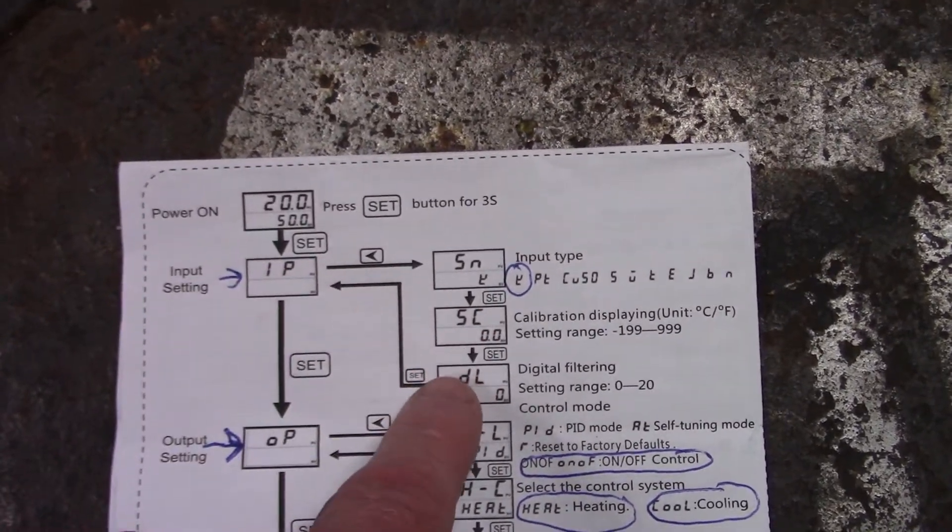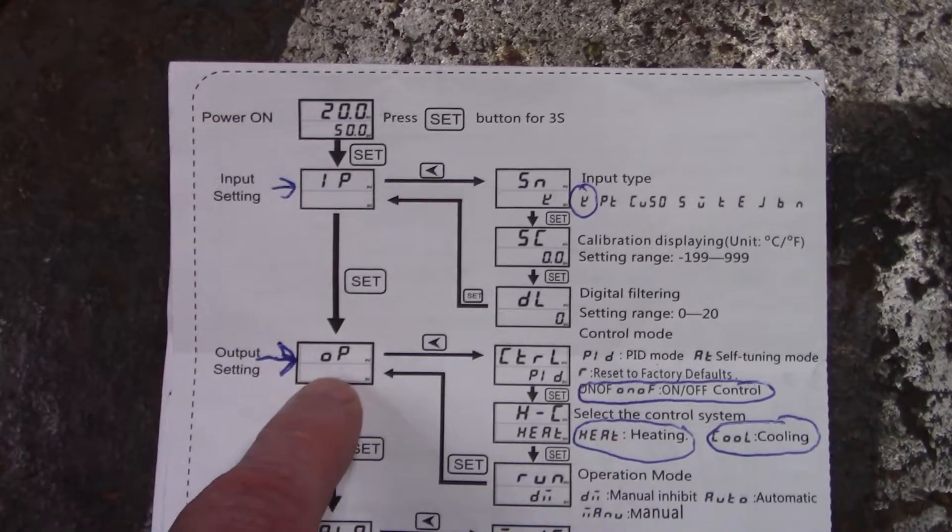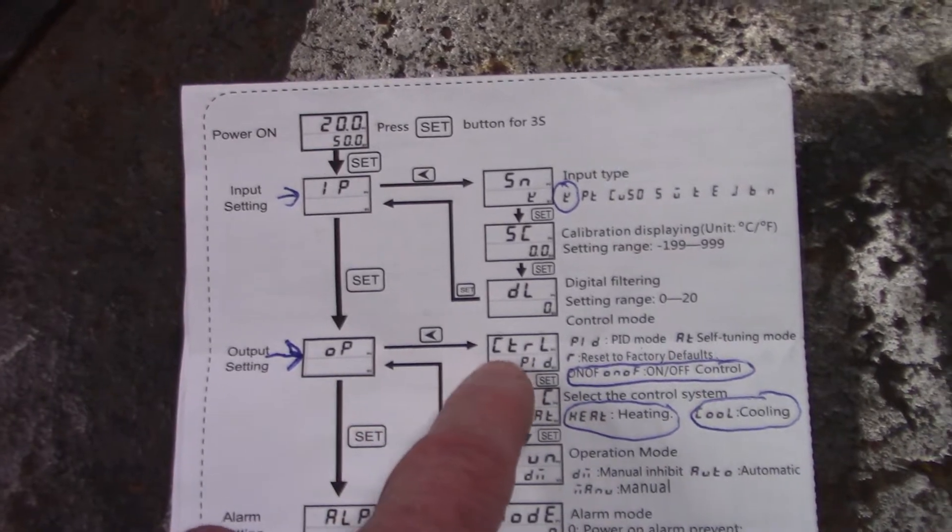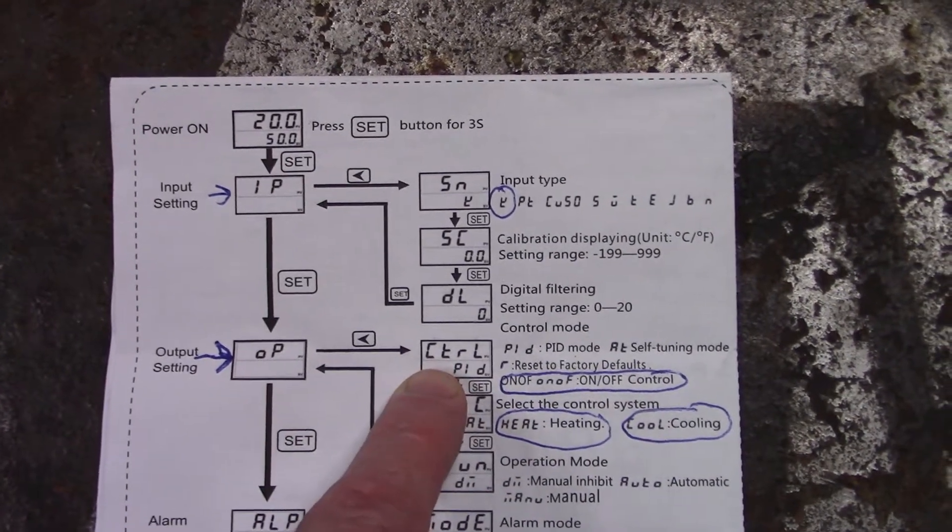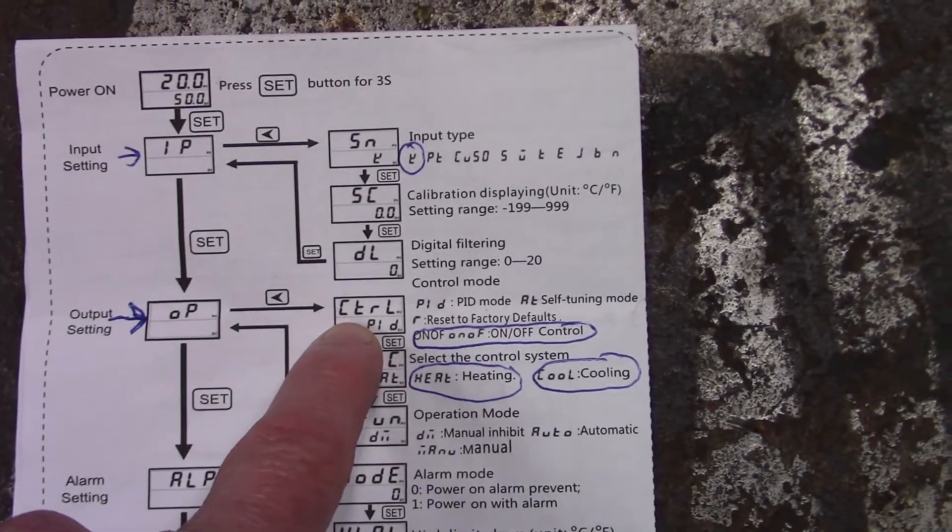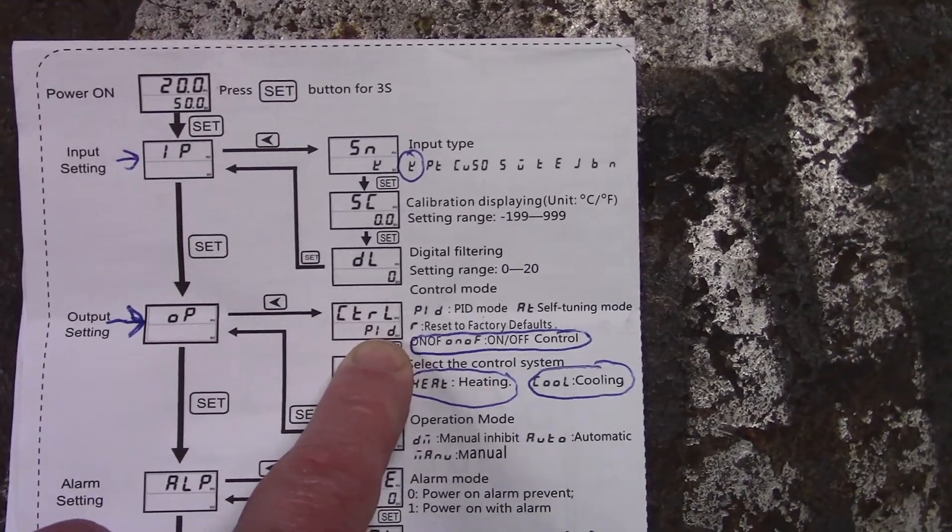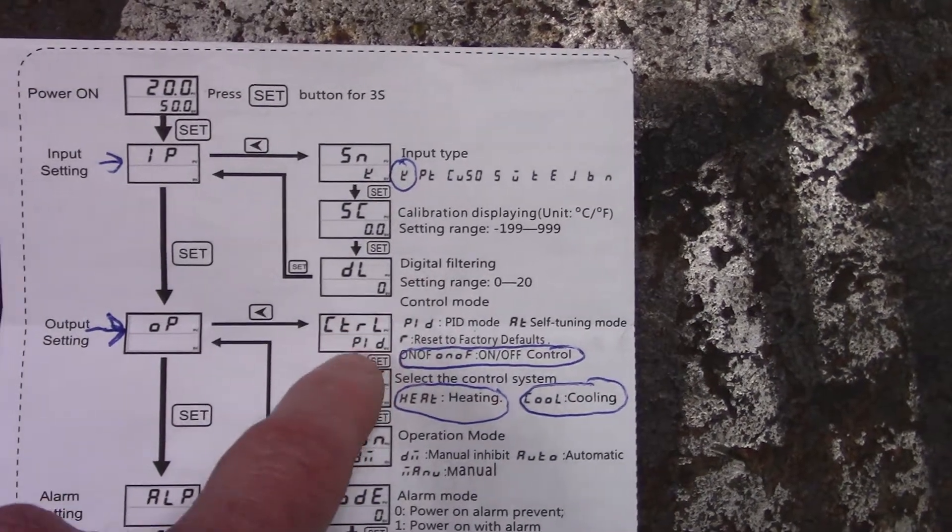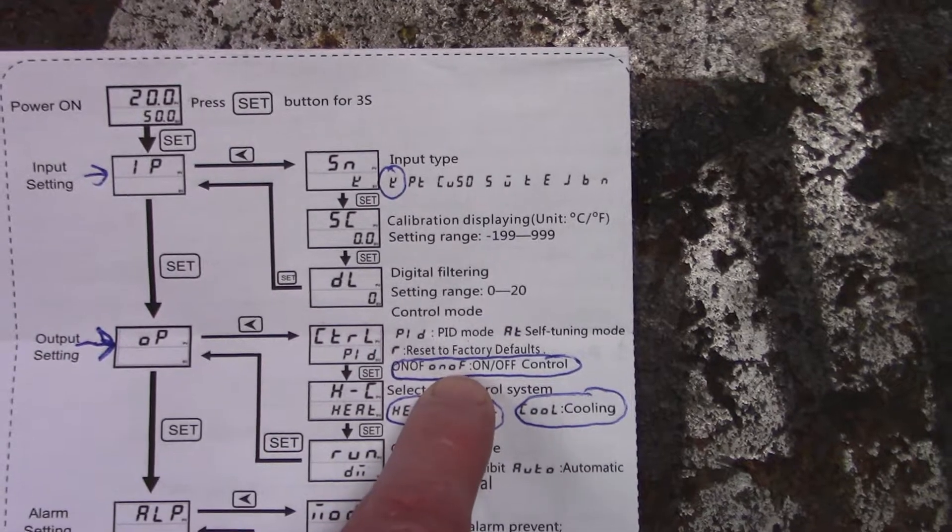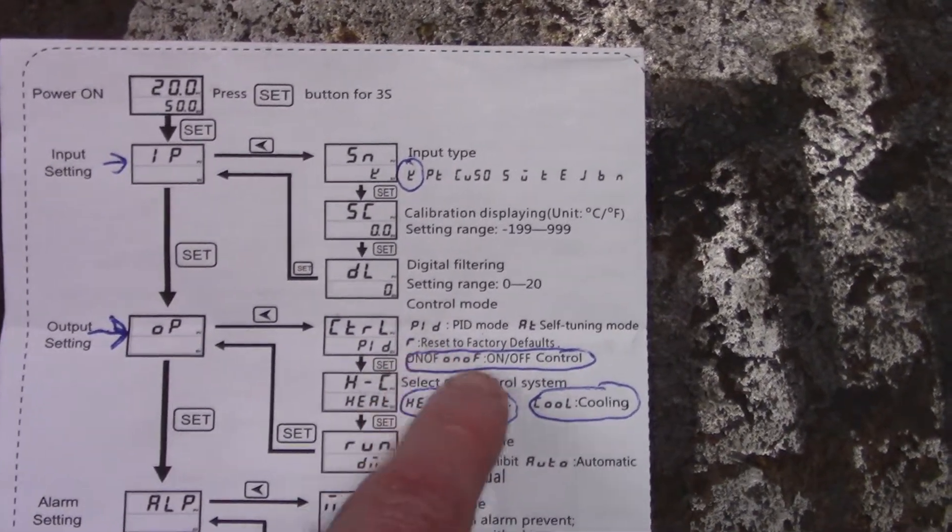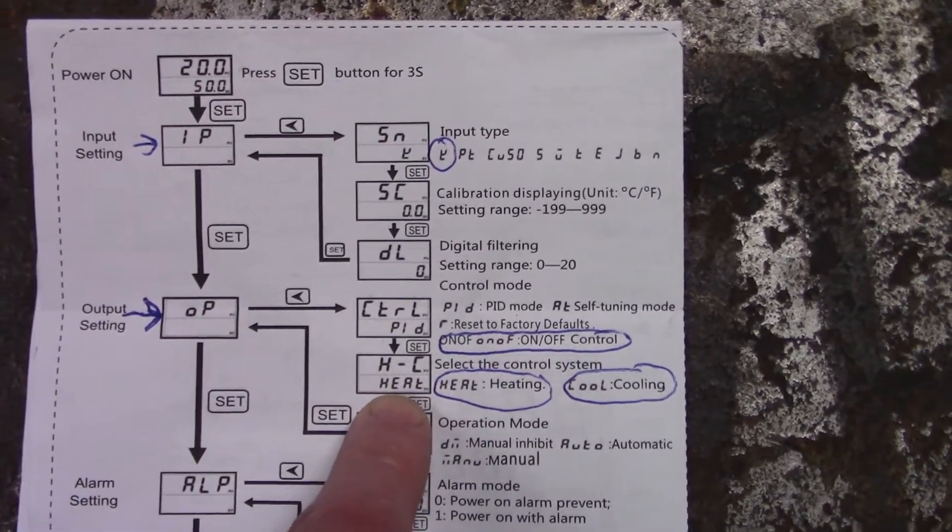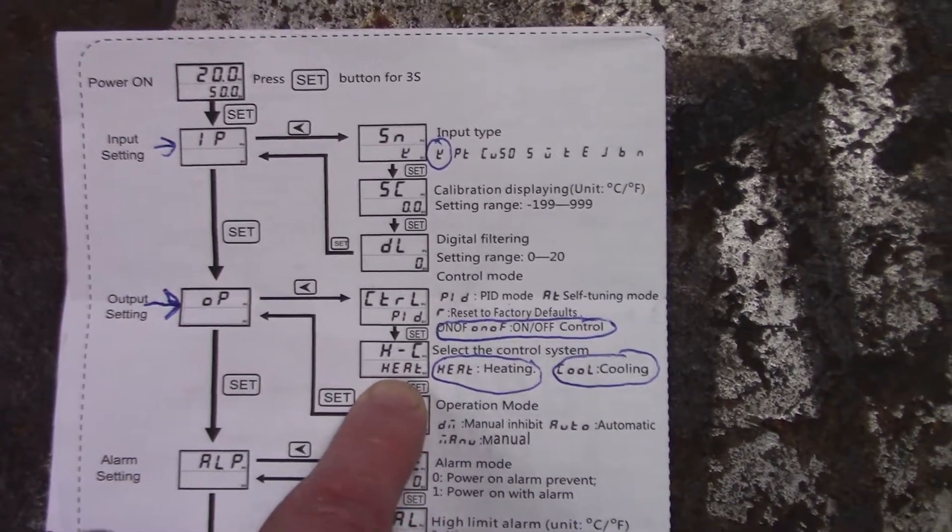Once you go through this menu it'll pop you back out here again and you'll go to the OP menu which is the output setting. For this control we're not going to use PID mode, it'll be set in PID mode from the factory, so you need to go into this menu and change it to on off.